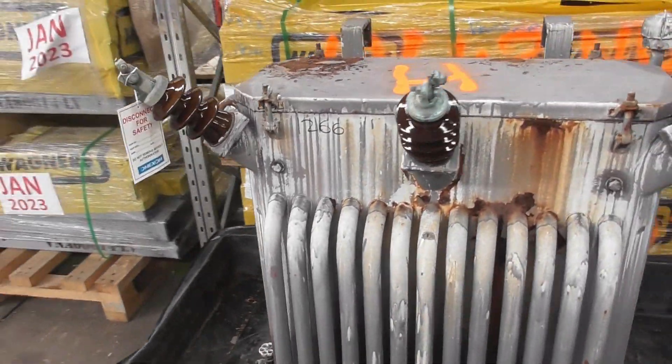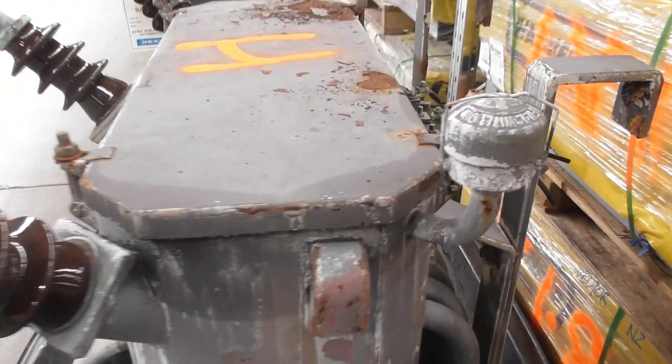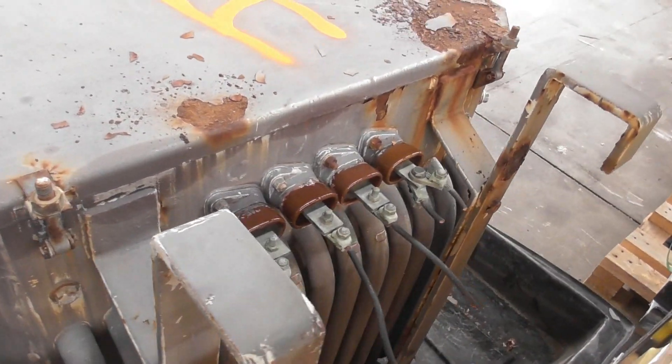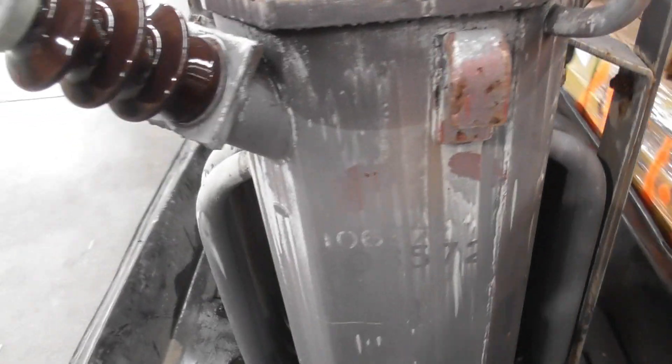We've got another old transformer being removed from service because of rust and probably rotten cross arms. This is quite a cool transformer — an old Ferranti. I'm going to do an insulation test on it and see how it is, what the condition is of the HV winding.